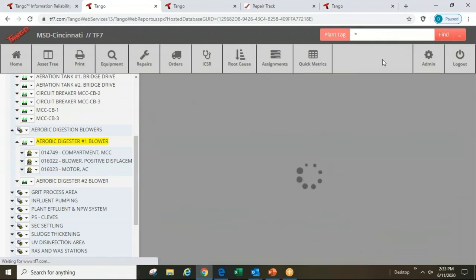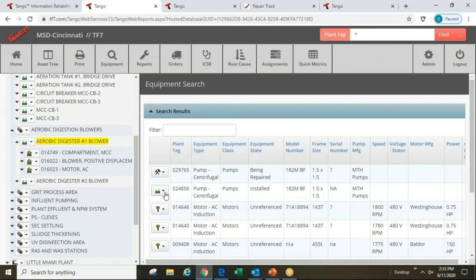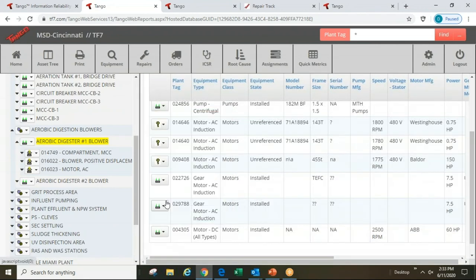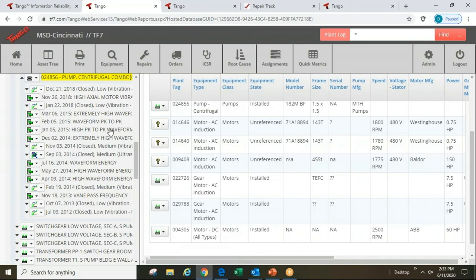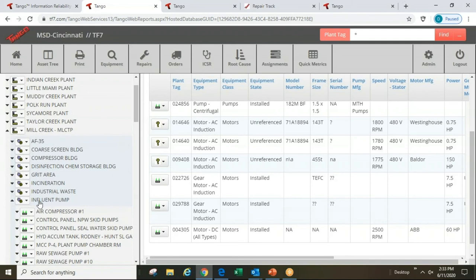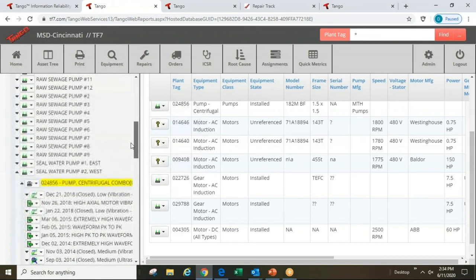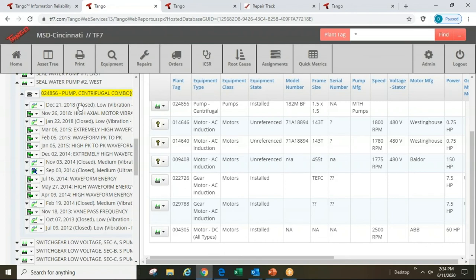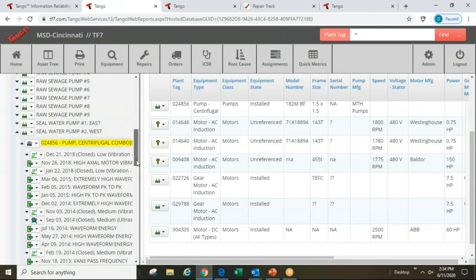Searching for a specific installed pump location, I can find it in the tree — it's part of the Mill Creek plant in the influent pump area, on seal water pump number two. It had a vibration problem that was closed in December 2018, another vibration issue in January 2018, and I can see the entire history for that piece of equipment.